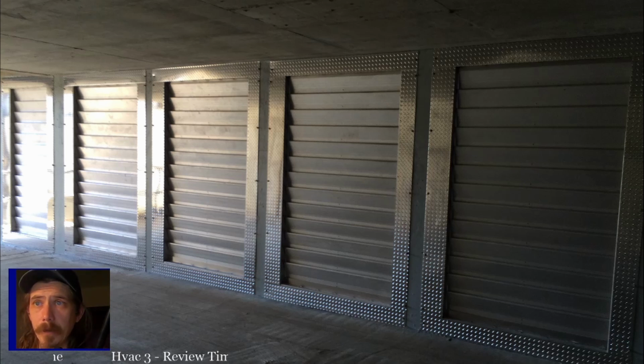the control panel is typically going to be removable. The benefit of that is what we talked about: you can take that control panel off of an existing drive, and if you're putting the same drive in, you can put that old control panel on the new drive and upload all the parameters from the old drive to the new drive. That's your primary benefit from having that removable control panel.